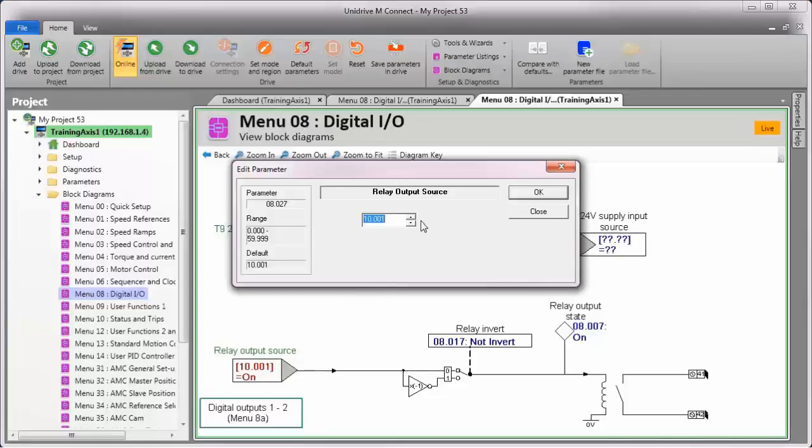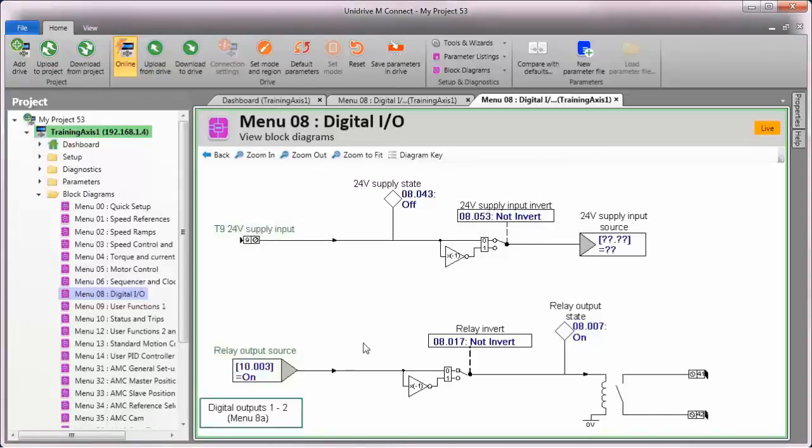For this example, I'll choose to use menu 10, parameter 3, which will activate the relay whenever the motor is at zero speed or frequency.